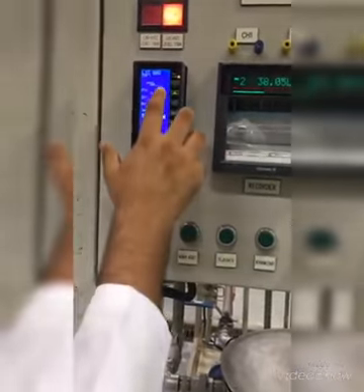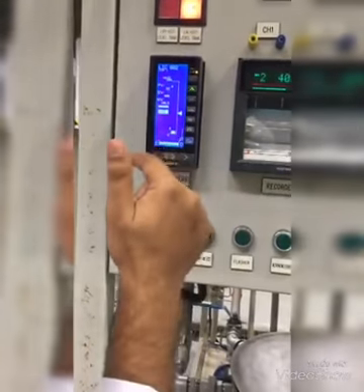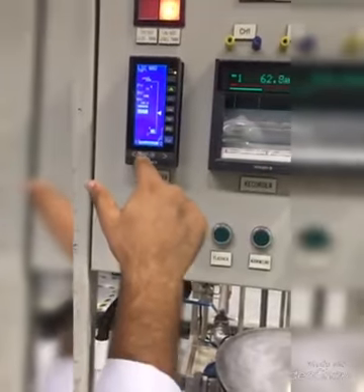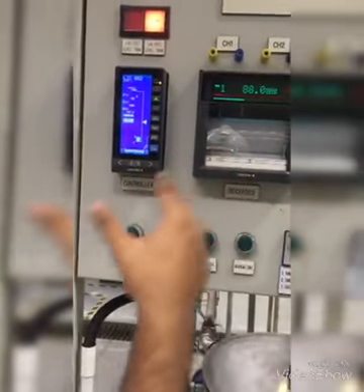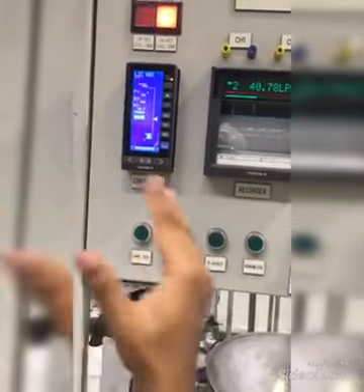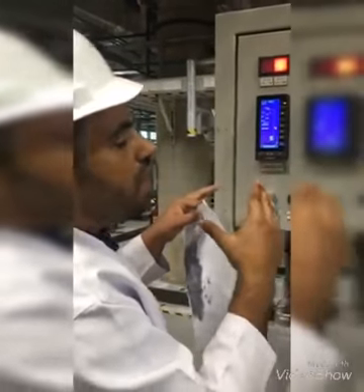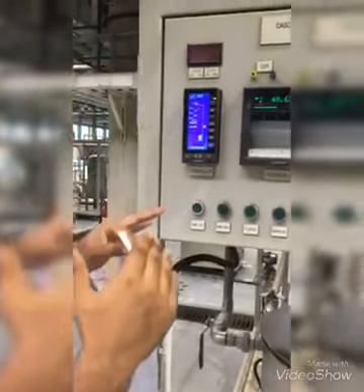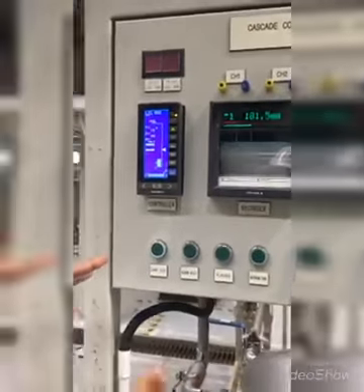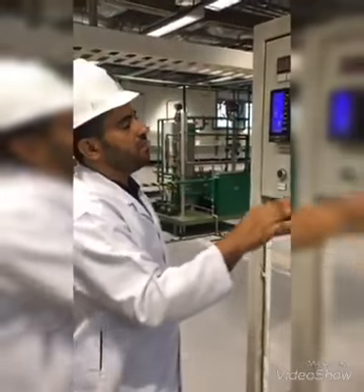Actually, when the PV value is stabilized at 400, you decrease it to 200 in order to see the response. So in every setting you have to change your PID values in order to see the objective of the proportional action, and also the integral action and derivative action.